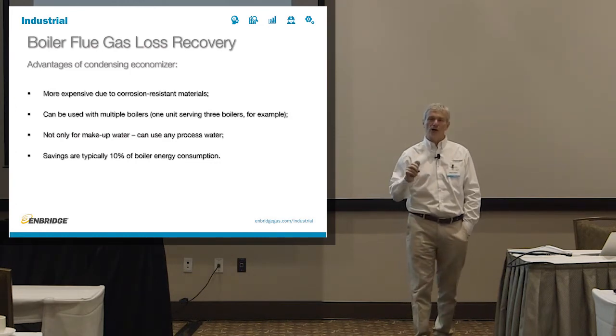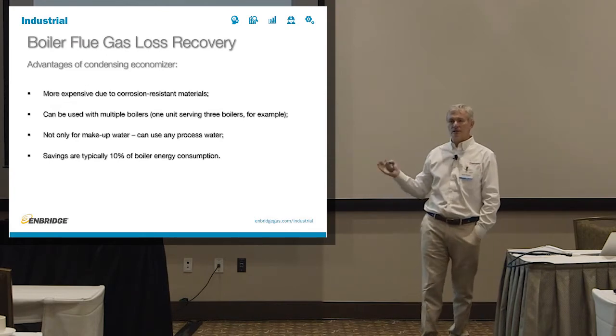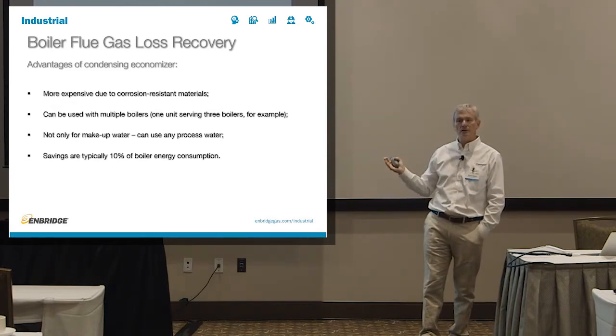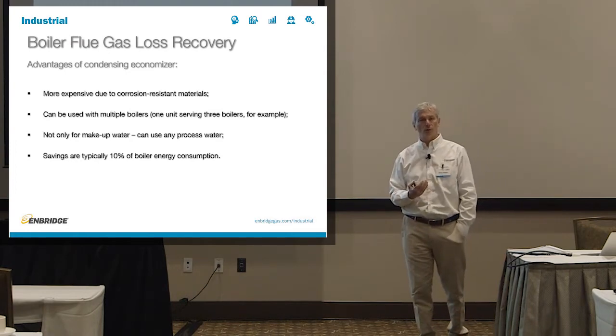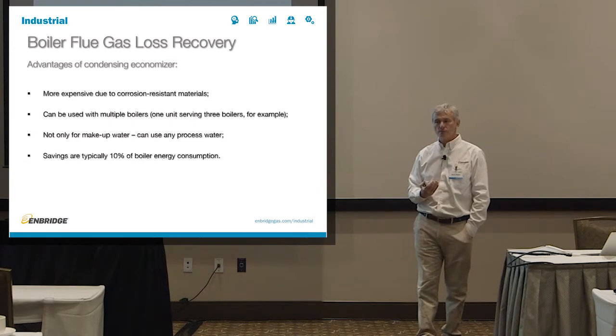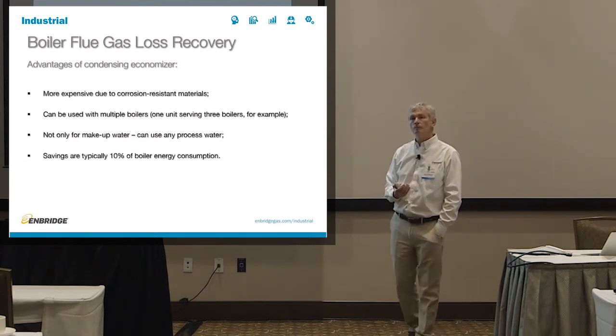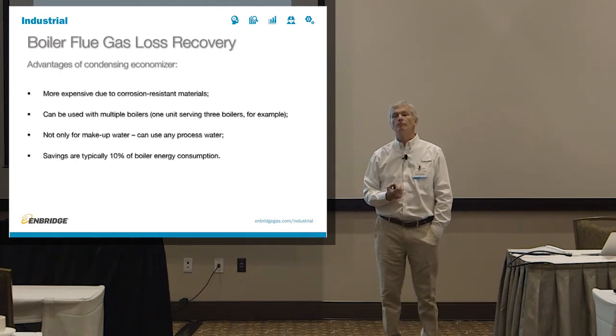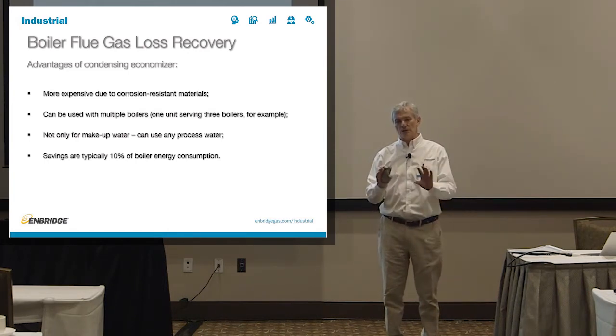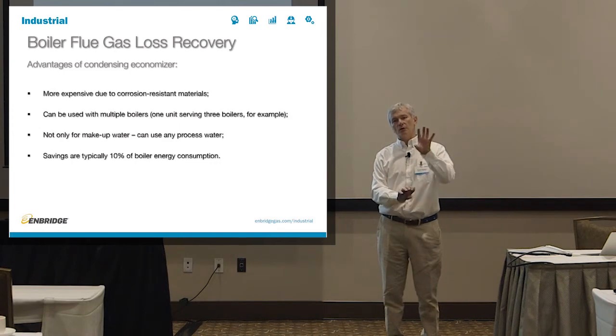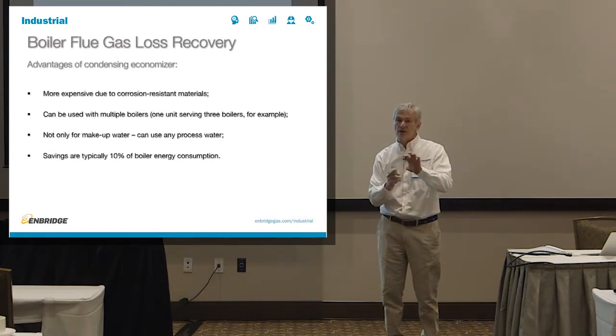If you're starting from scratch, you have no feed water economizer, and you have a good solid heat sink, you can skip the feed water economizer, you can go straight to the condensing economizer and save 15% of your boiler consumption. In proper application, you have a feed water economizer that saves 5% and a condensing economizer that saves 10%. If you don't install the feed water economizer, all the energy goes into the condensing economizer, and assuming it's properly sized, it will recover the same amount of energy as the two economizers.